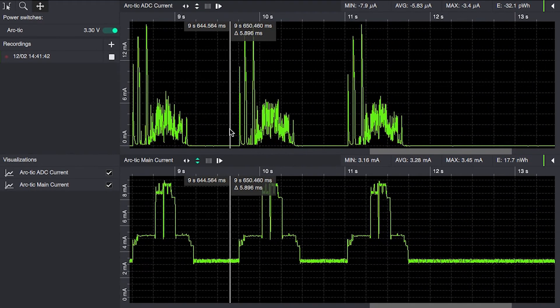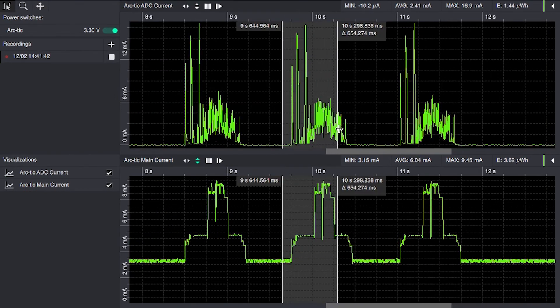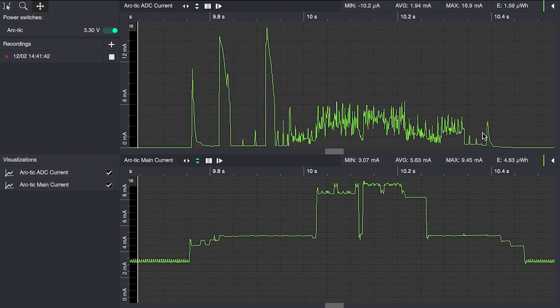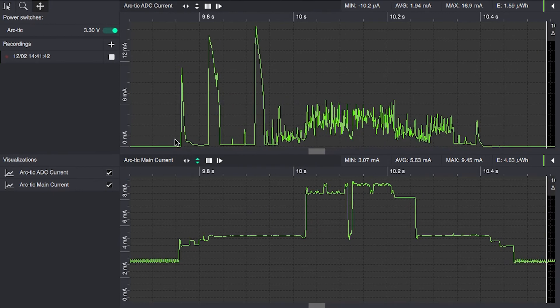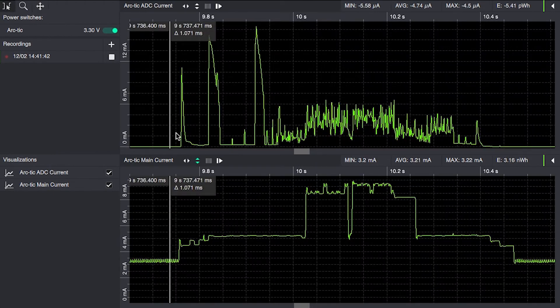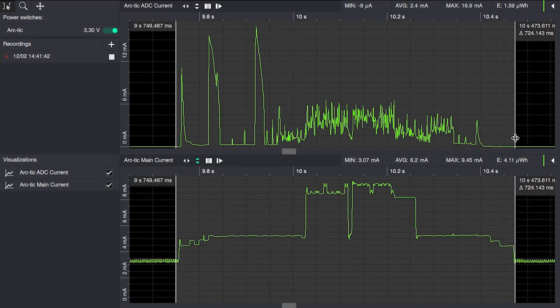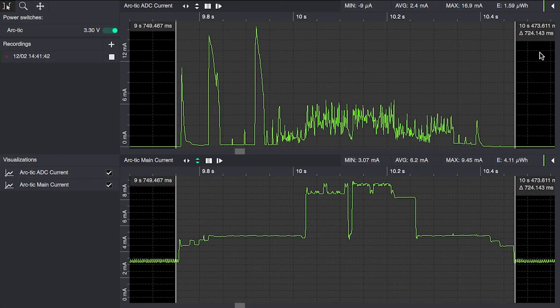We freeze this and zoom in to one of these recordings. We will see that we have now reached a peak of 16.9 milliamps, which is actually less than the specified value of the display. This is a process that is actually running for 724 milliseconds.